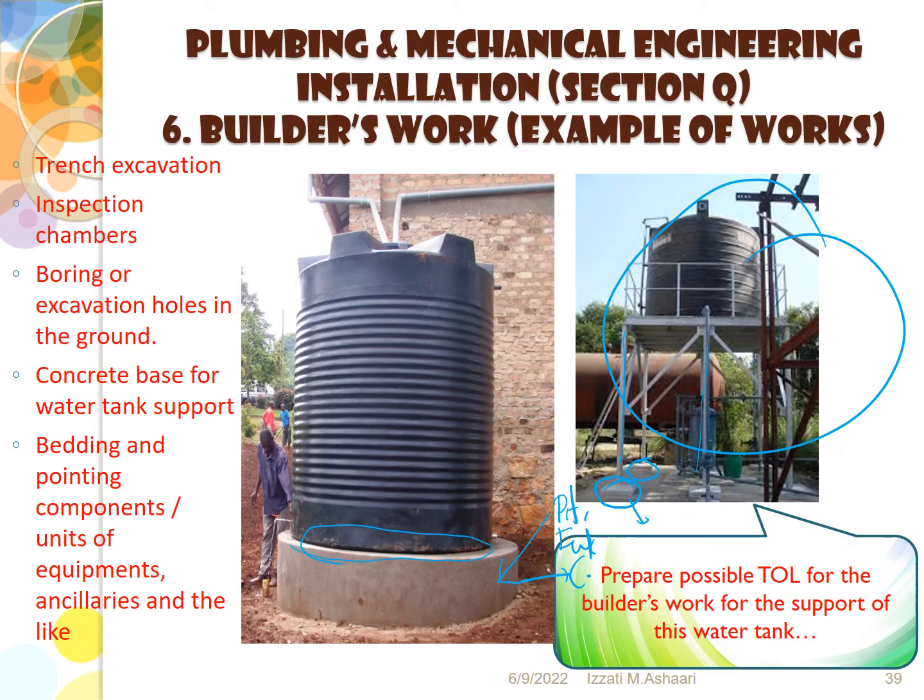Now, this is the example on the left-hand side, the example of the item to be measured for the builder's work. There is the possibility to have the trench excavation, boring or excavate holes for you to install the concrete plinth or the concrete base. And then there is the possibility that the bedding has to be installed below the concrete base. And then after that, for this particular item, there is the possibility to install the formwork and the bar reinforcement if there is detail given for this particular item.